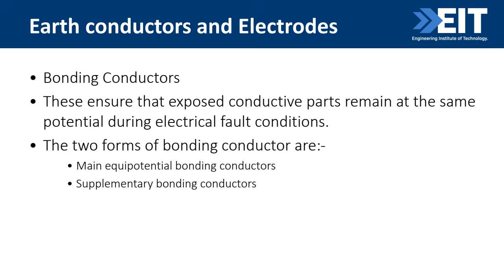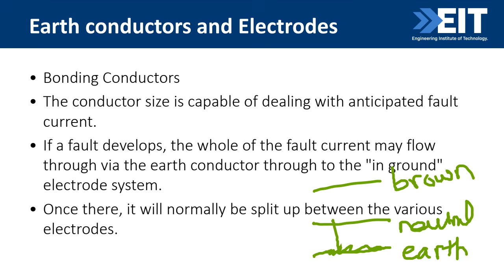Is neutral the same as ground, earthing? Can everyone please text and answer in that box? It's not the same thing, no. So basically the idea is that you have a neutral cable and you have an earth cable. So the green-yellow typically here you'll see is earthing, and neutral will be blue, and live is brown - that's in Australia. And we want to obviously connect the neutral down to earth, but they are different.